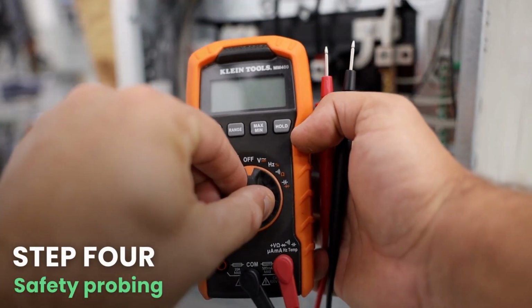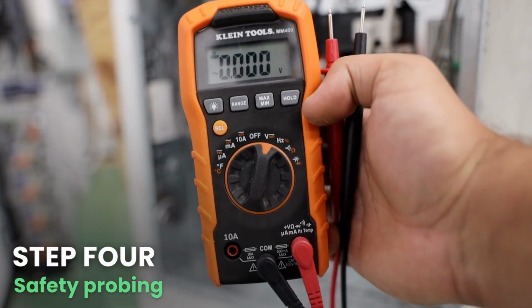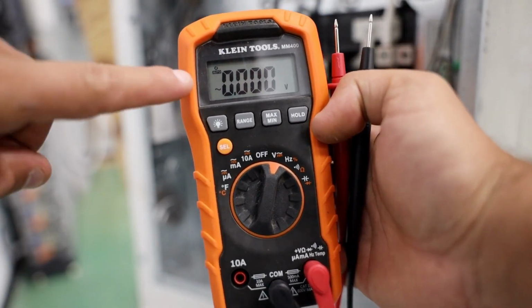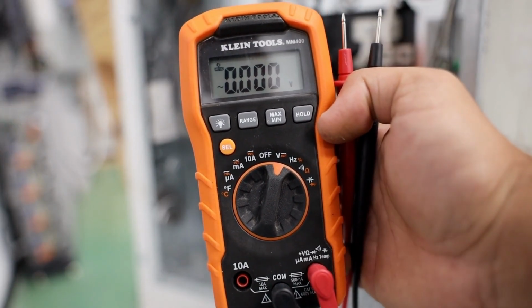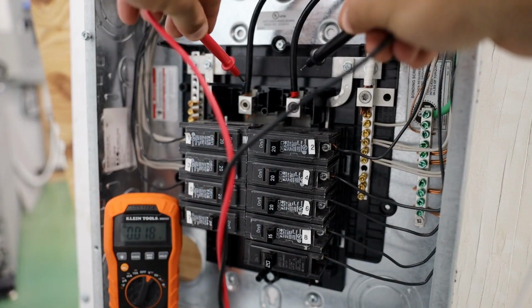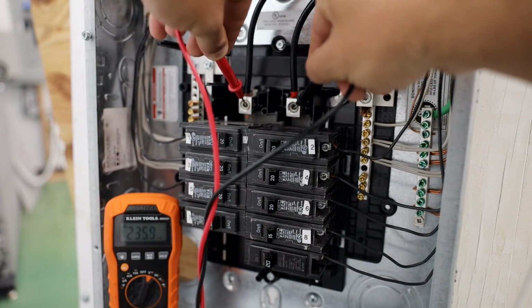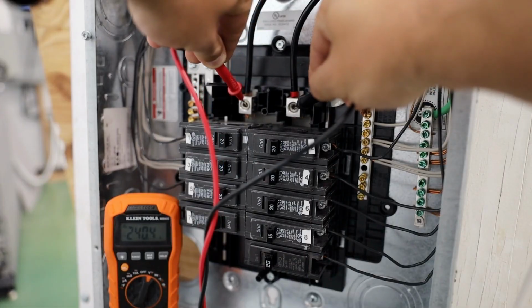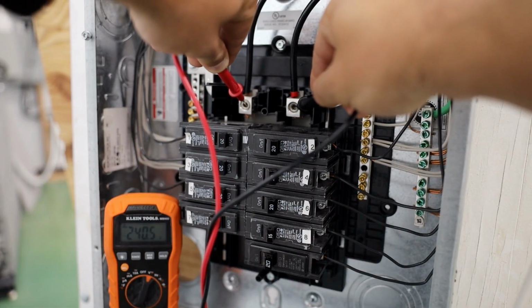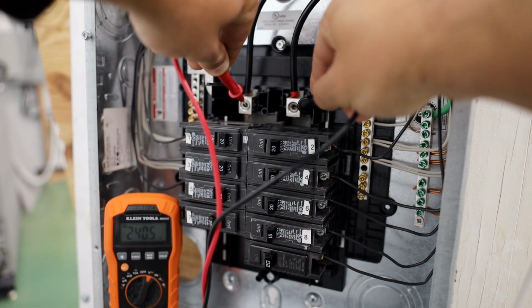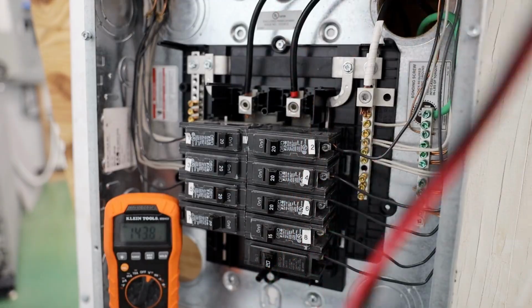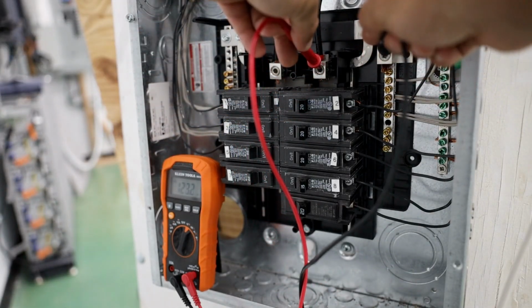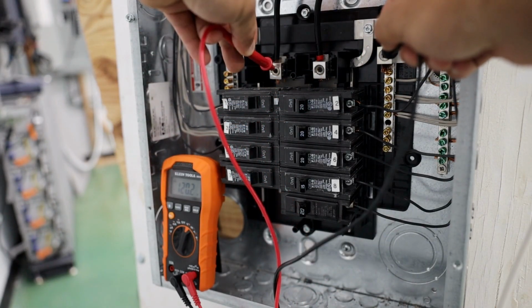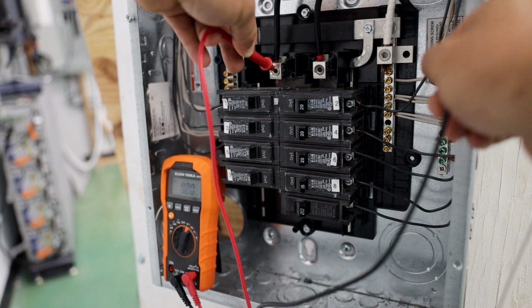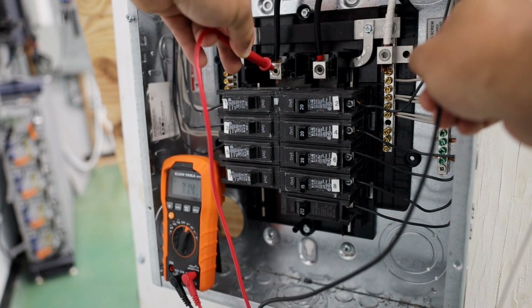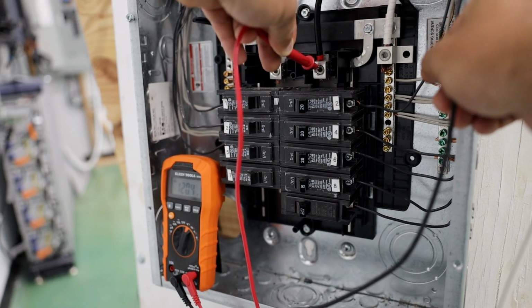Take a multimeter and set it to measure AC voltage. Make sure that it is displaying the correct measurement unit. Next, carefully probe each main ports of the AC load panel. Since this is a typical residential single split-phase configuration, you should be getting 240 volts from line 1 to line 2, 120 volts from line to neutral, and 120 volts from line to ground. Reminder, please use personal protective equipment when performing this procedure.